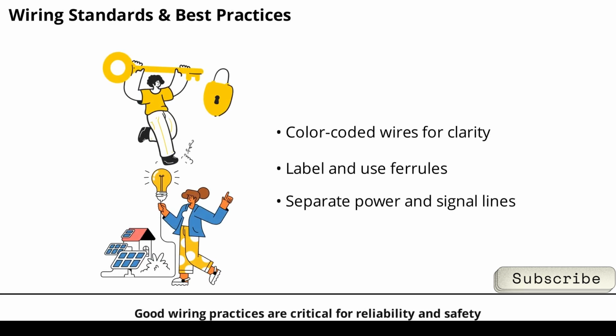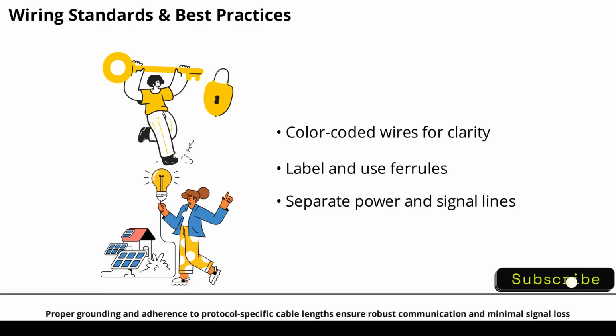Good wiring practices are critical for reliability and safety. Inside the panel, use color-coded wires: red for 24V, blue for analog signals, black for ground. Label every wire and use ferrules for secure connections. Route cables neatly using troughs or ducts, and always separate power and signal wiring to reduce electrical interference. For field wiring, shielded cables are a must for analog signals, especially 4-20mA loops. Proper grounding and adherence to protocol-specific cable lengths ensure robust communication and minimal signal loss.